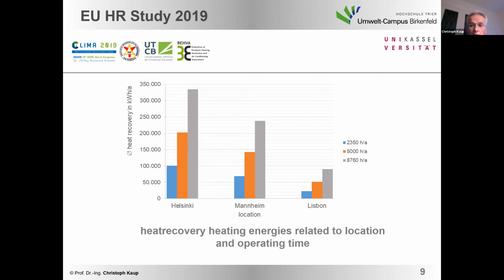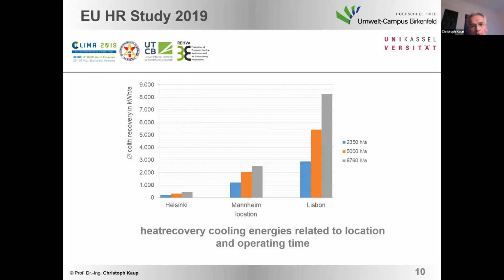But you see that there's not only an influence by the climatic conditions, temperatures, climate zones, you still see that there is a big influence in operation time. For example, if you have an office in Helsinki, that will have roughly more or less the same possibility of recovered heat as a hospital in Lisbon, for example. You have the same range depending on the operating time.